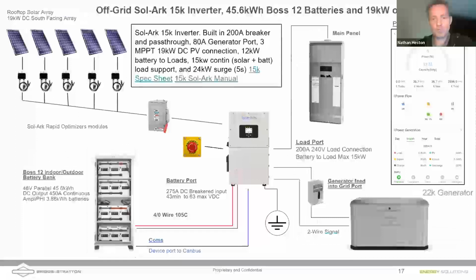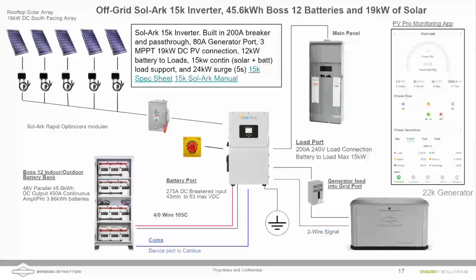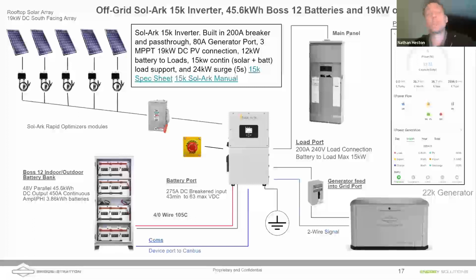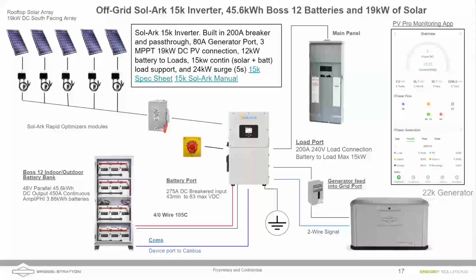Daniel, any more questions? Well, Mike had mentioned, can the grid input be used for both generator and grid via a transfer switch of some kind? And I think that it's going to need to be reprogrammed. And just so we're clear, I think the answer is no there, right? Because, well, I'm not certain of that. So I think we'd have to defer to Sol-Ark's technical support there. And just so we're clear, we're not saying that you can't AC couple solar into the generator port. I think the discussion here is that if you have both a generator and AC coupled solar, and you have grid and you have load, how do you use two inputs into one input port on the system?